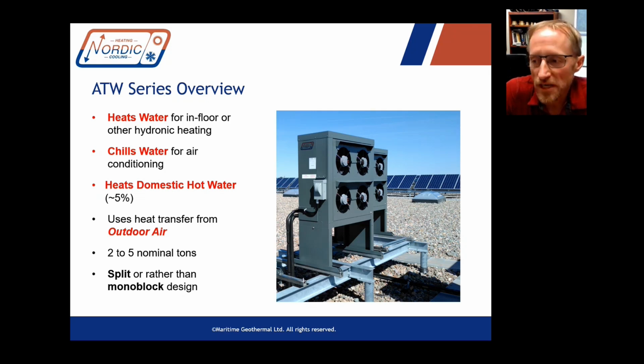No, you're limited to exchanging heat with the outdoor air for the main cooling and heating functions of the heat pump. So with the dedicated domestic water preheating, you're actually switching the heat pump into cooling mode, and it has control for a 3-way valve to direct the main outputs to the cooling tank, and then you're cooling that tank until it reaches its set point, and then checking the hot tank and seeing if that needs to be heated. Maybe because someone's been doing the dishes or had a shower or whatever.